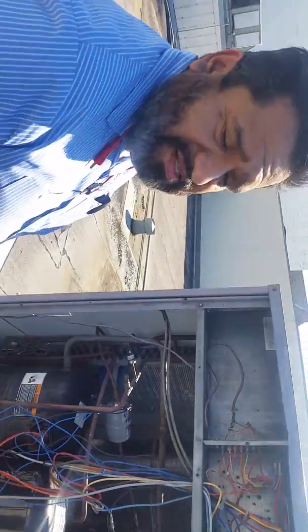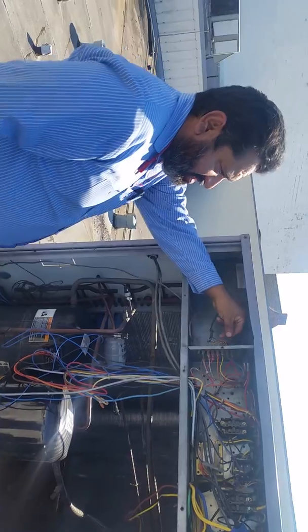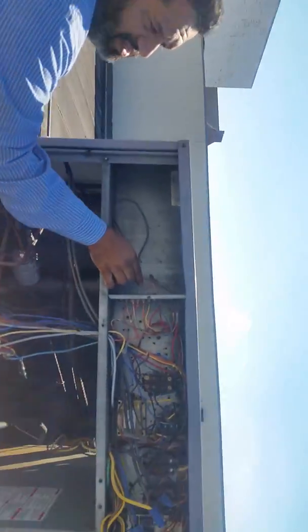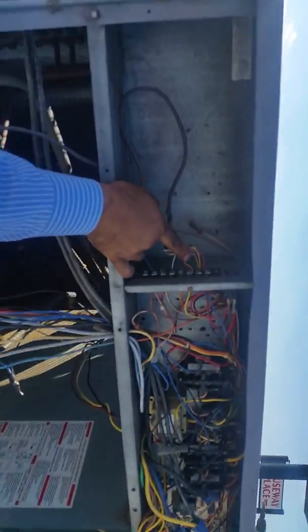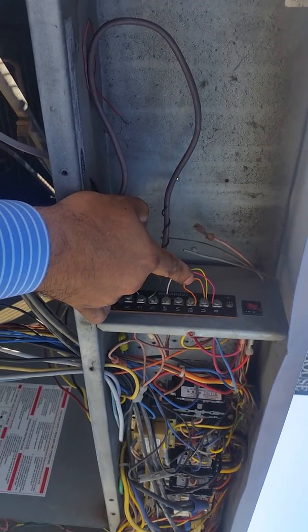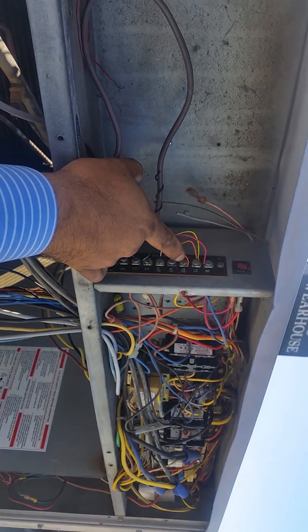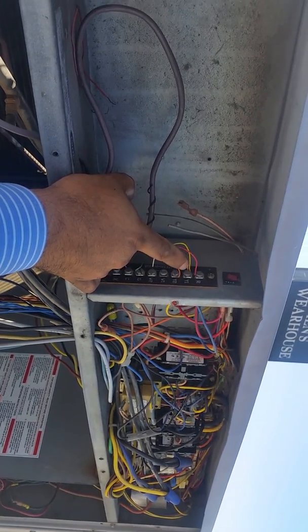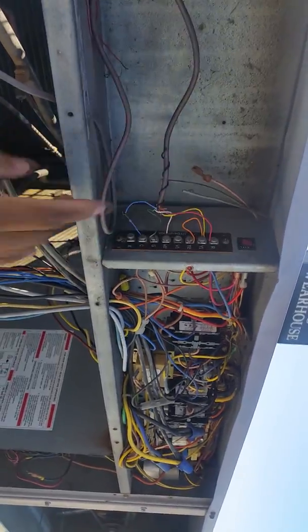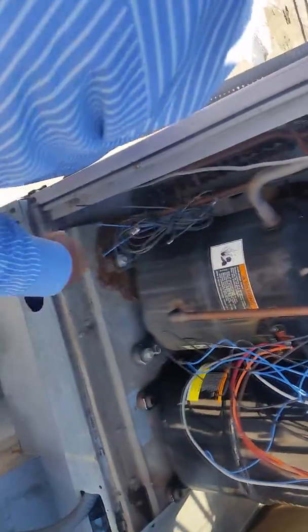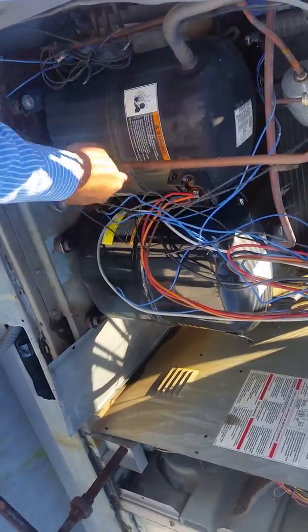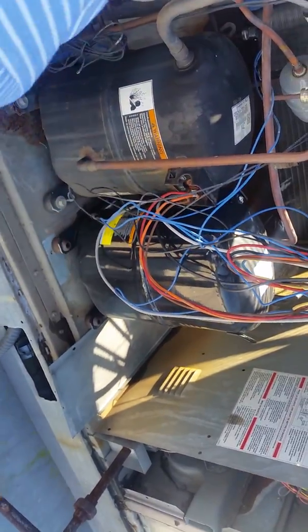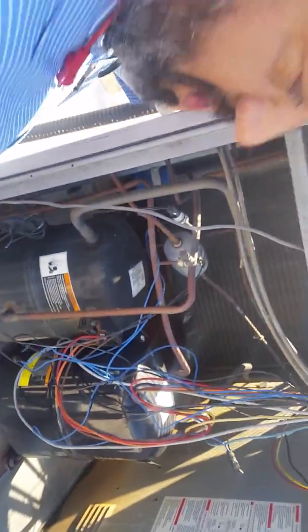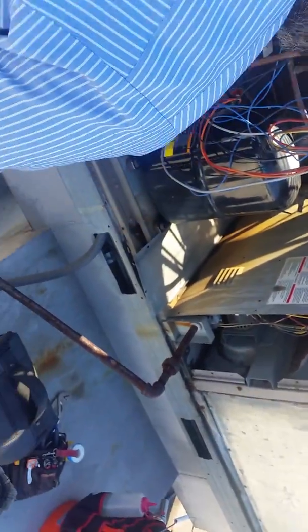Found this unit frozen up just a minute ago. What it is, I'll show you. They got first and second stage jumped. So what that means is that when first stage comes on, second stage comes on automatically, whether it needs it or not. That needs to be corrected. Some of this wire right here needs to be corrected. I'm going to be putting some tape here in the meantime, but we need a cap for that or something, just in case of the rain or anything.